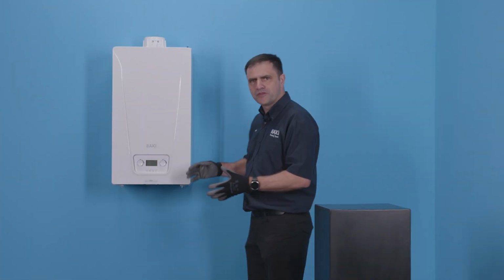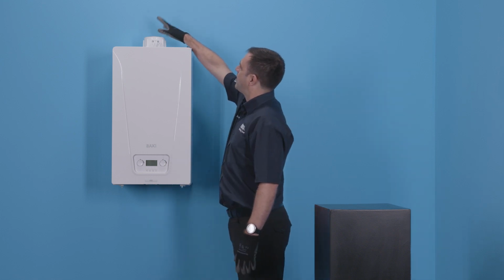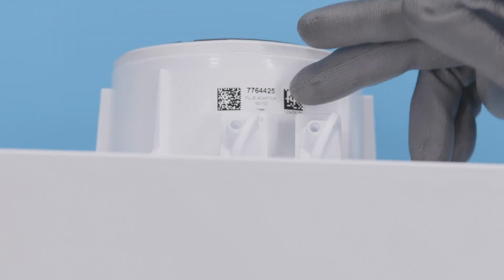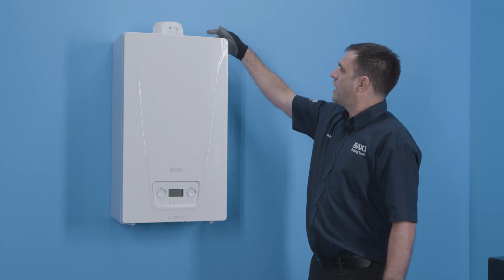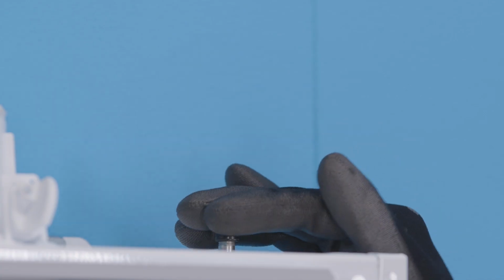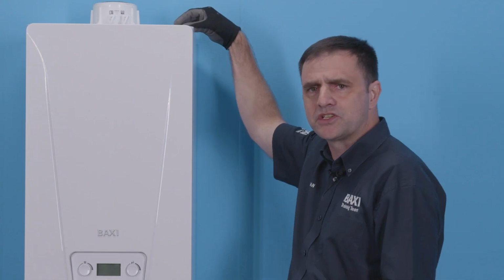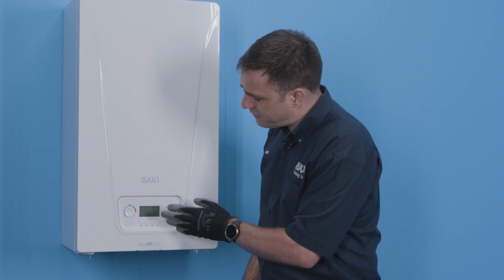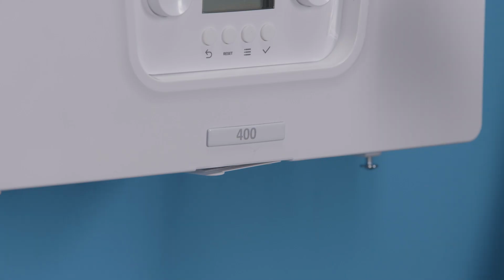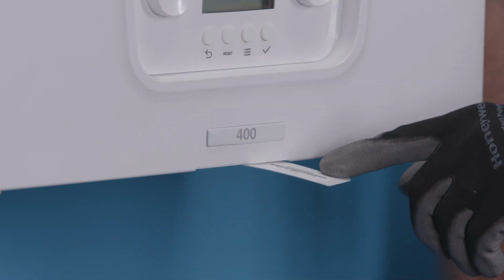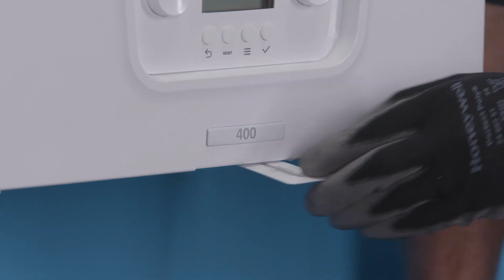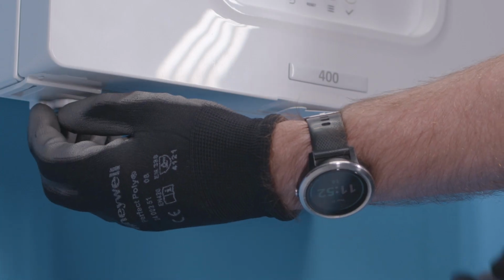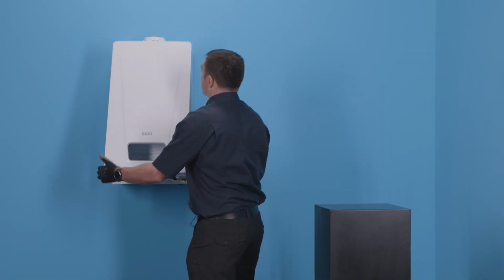Okay, so let's give you an overview of the boiler. At the top here we have our centre flue, including the test points for doing your commissioning. Outside here we have a Schrader valve, outside of the case, making it easy to test your expansion vessel. Further down we've got very simple to use controls for the customer. For you, we have the barcode here to register the boiler. To remove the case, simply loosen the 2 screws at the bottom and pull the case away.